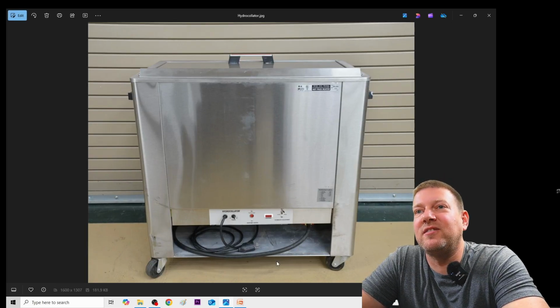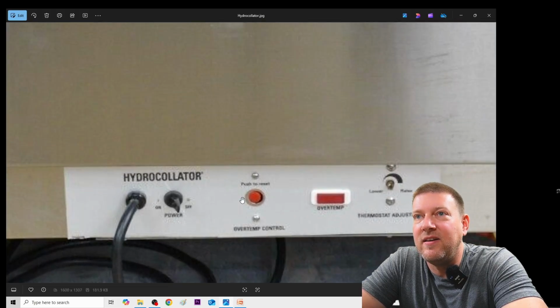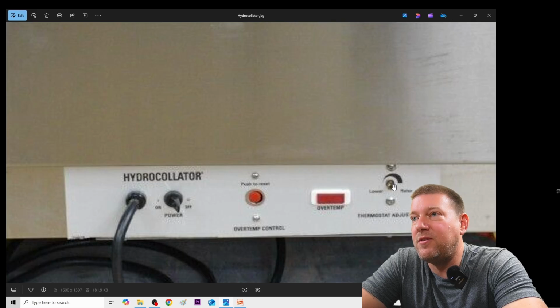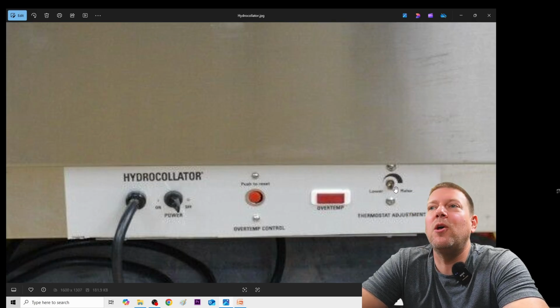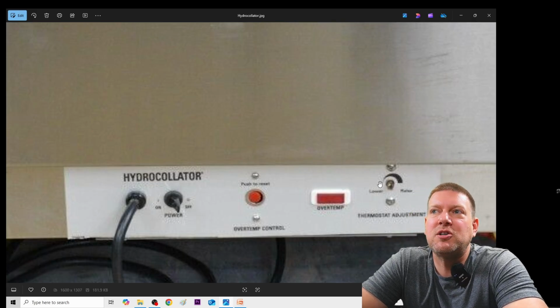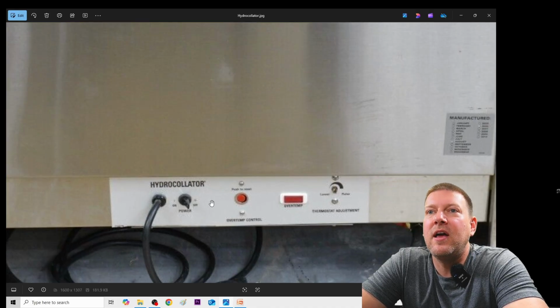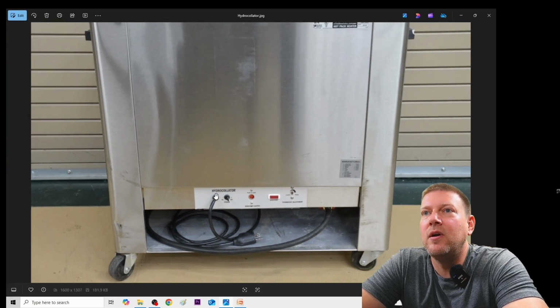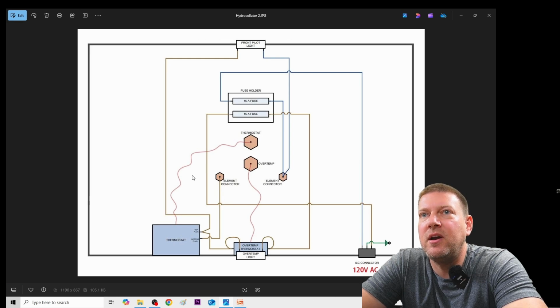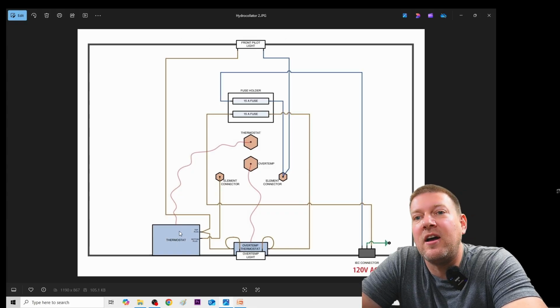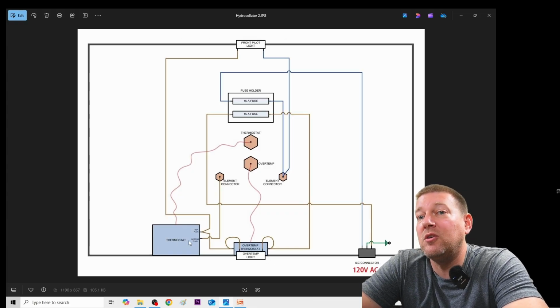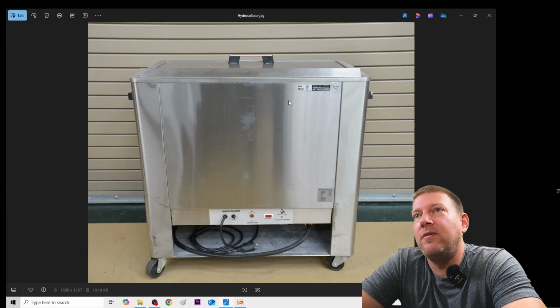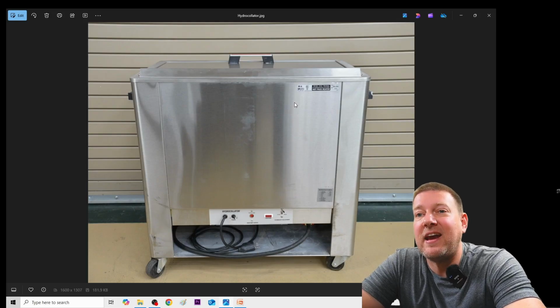That's what the Hydrocollator looks like. You can see the control panel down here. Yeah, simple, over temp control, that's just resettable. And look at this right here, the thermostat is just an analog spring-loaded dial that puts more pressure on a little diaphragm. That diaphragm is actually controlled based on pressure, which is this guy right here. So there's a little spring-loaded diaphragm in here, and all you're doing is increasing the amount of pressure on that spring, which prevents it from tripping early. And that's how it controls its temperature, and it's worked for decades. Love these guys, I've done multiple videos on them.